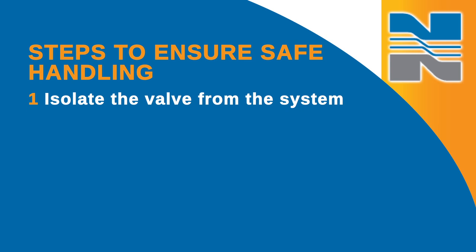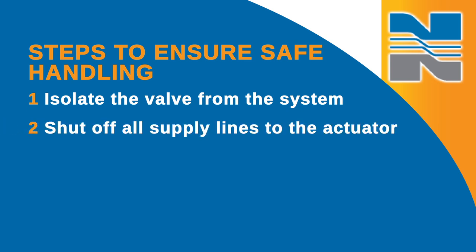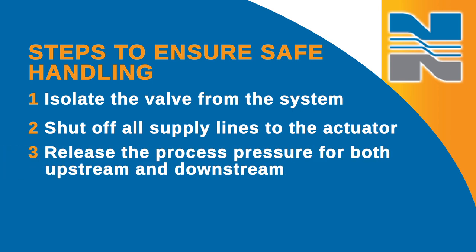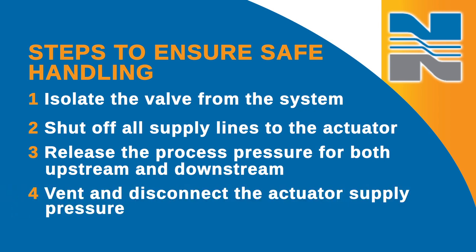First, isolate the valve from the system. Then, shut off all supply lines to the actuator and release the process pressure for both upstream and downstream. Finally, vent the actuator supply pressure.